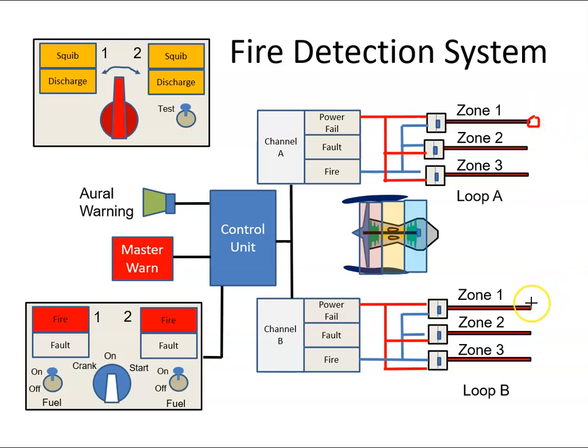We should also get a detection in Loop B. If we get a fire, what we want is an AND gate here, so we have a fire in Loop A and Loop B confirmed.